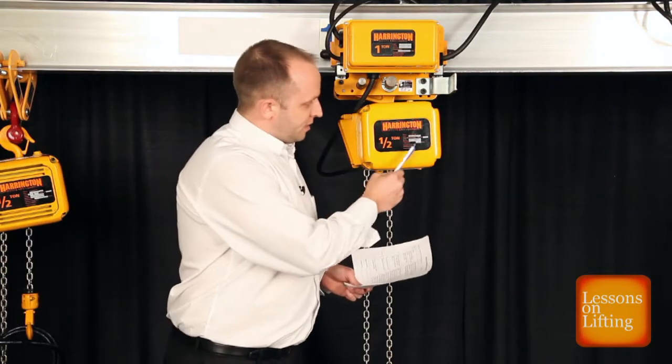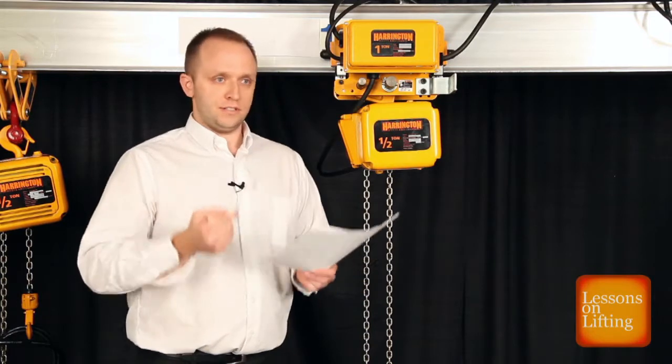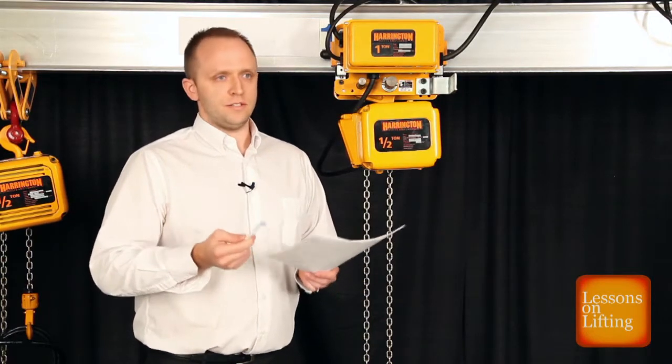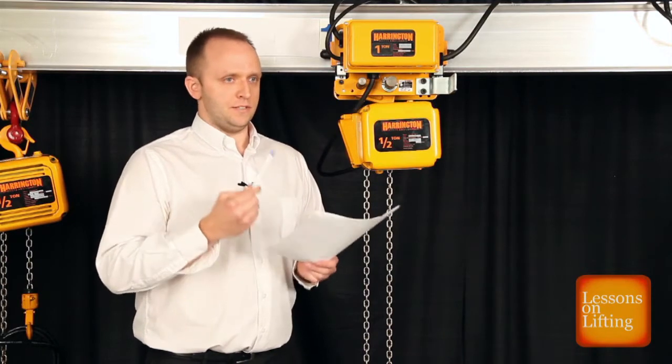If you have two letters, for example LD, the D, the second letter, tells you that it's a dual-speed unit, so a voltage change is not possible, again, because the VFD inside is voltage-specific.